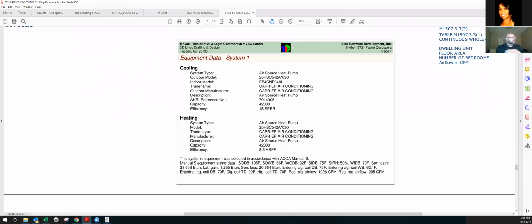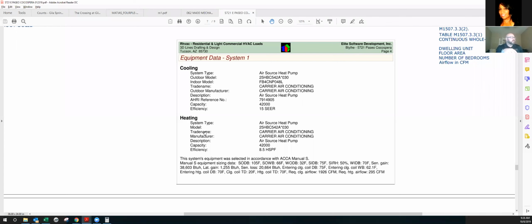All it means is that we have to communicate that. So what we would do in our quote in this example is say, exception, equipment provides 1461 CFM, not 1926, as specified. We'll just let them know, you want almost 2,000 CFM, and our equipment doesn't do it.